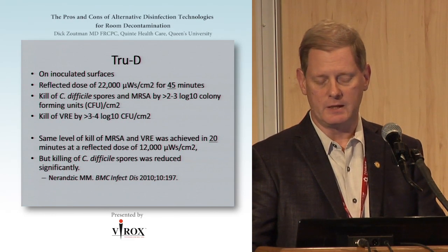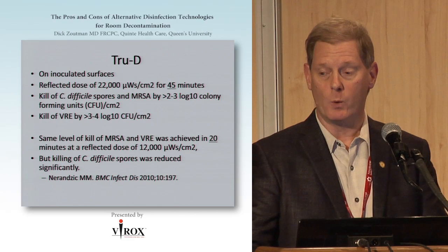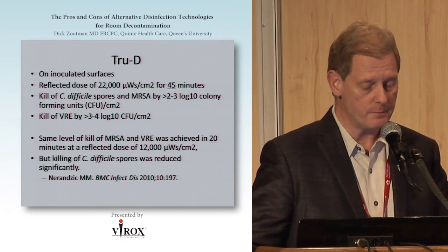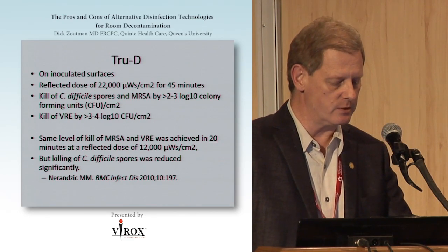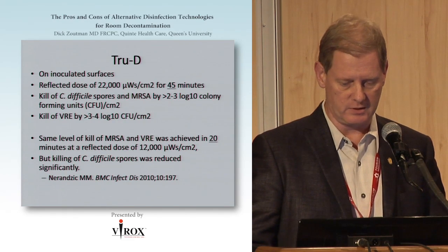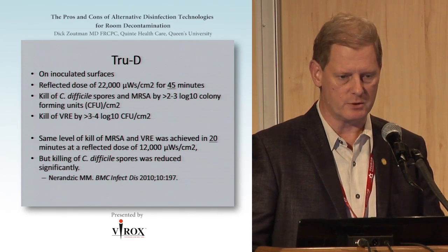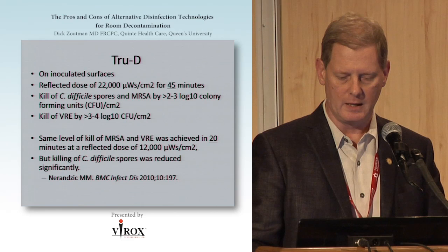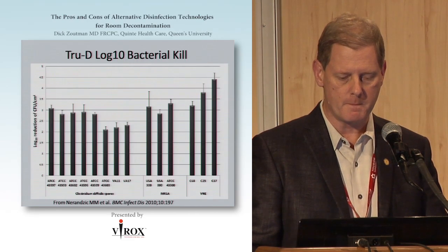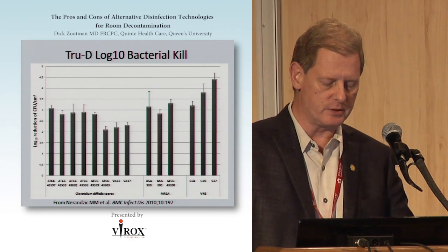They had the same level of kill of MRSA and VRE with a 20-minute exposure. They reduced the exposure. However, they found that the C. diff spore kill was minimized significantly by a 20-minute exposure. So time is an important variable, as is the distance.